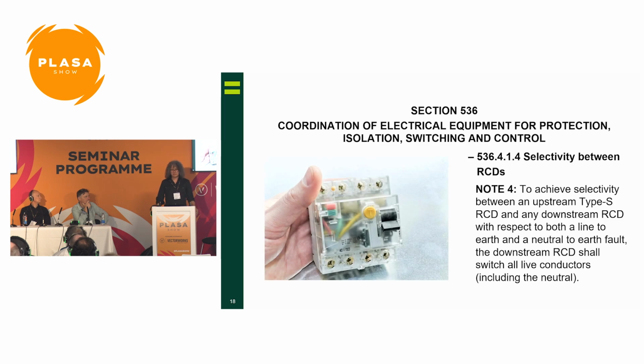Next thing to look at is selectivity between RCDs. This requirement, again, is where the upstream device is a time-delayed RCD and the downstream device is not time-delayed. So you've got RCDs in series. Now, what this is saying is the downstream device should operate first, but when it does, that device needs to be a multi-pole device to switch all live conductors. And by live conductors, it means the phases, or the lines, and the neutral conductor too. Because if you draw the circuit diagram out, and the downstream device is just switching the line conductor, then depending where the fault occurs, you can get currents flowing, and therefore you haven't removed the fault. So the downstream device in this instance needs to be a multi-pole device.